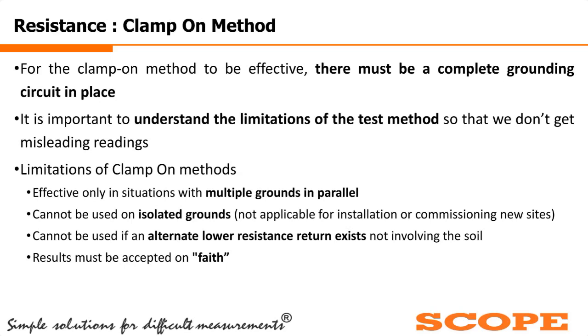So the return paths which are involving the soil. So this type of limitations for this type of clamp-on method, and this clamp-on method is not that much accurate as the stake type of methods, in which we are using the practical grounding rods for the measurement. So this clamp-on method is very poor, and these results must only be accepted on faith.